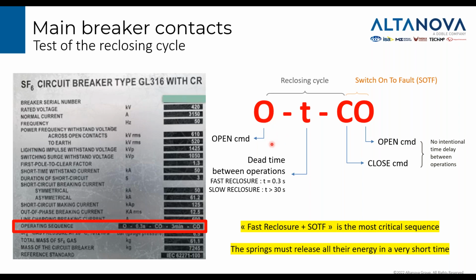O means open command. T is a waiting time, or to be more precise, it is called a dead time between the open and the first close operation. This time can be quite fast, less than 1 second, let's say 0.3, 0.5 seconds. In this case, we are talking about a fast reclosure, but it can also be long, higher than 30 seconds, can be a minute. In this case, we are talking about slow reclosure. This close command and open command without a time is representing the switch on to fault logic. So this means that there is no intentional time delay between operations.